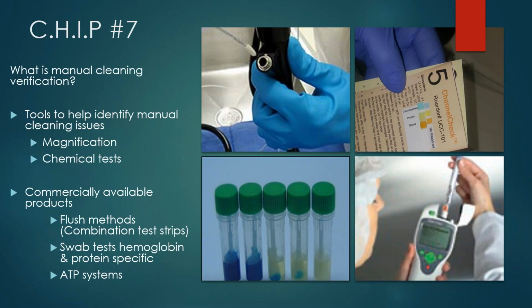Tip number 7 is cleaning verification. And what is cleaning verification? Cleaning verification in its simplest form is visual. We're all doing that already. We're actually taking instruments, holding them in front of our eyes, and looking for the debris that we can see. But debris getting down to, say, 0.1 microgram and in specific spots like the channels of endoscopes becomes very, very hard to see, if not impossible to see, with the naked eye.